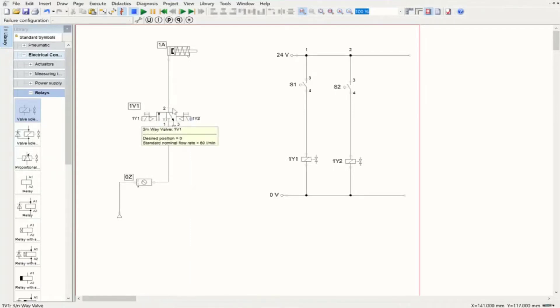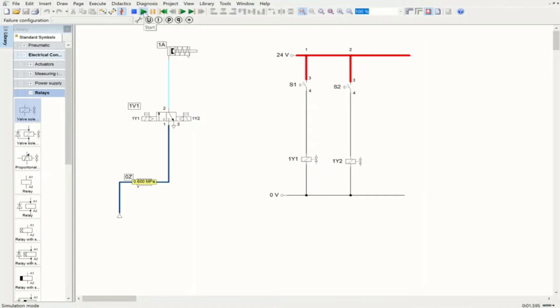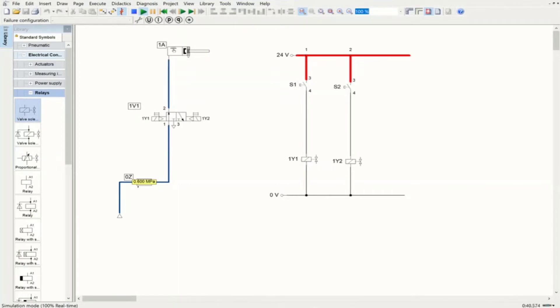We have the directional control valve communicating with the electrical circuit. Starting the simulation, the system is ready for operation — this is a normally closed valve, so air cannot pass until it is electrically actuated. That depends on S1: if I turn on S1, 1Y1 is going to be energized, the circuit shifts to the second position, air can pass through and gets inside the cylinder, and the advancing process starts. We reach the fully advanced position.